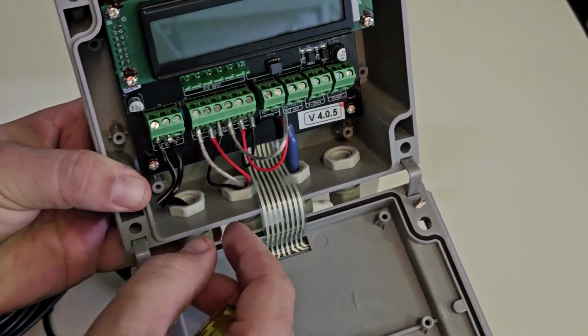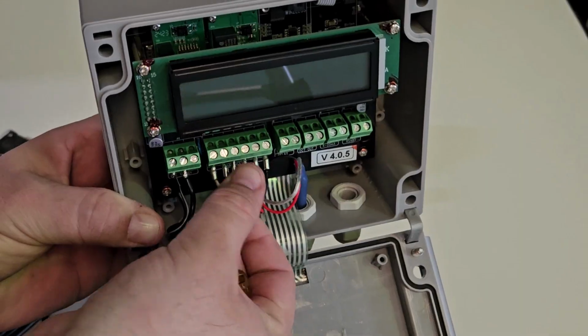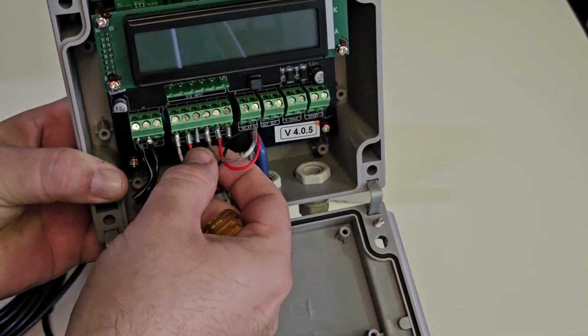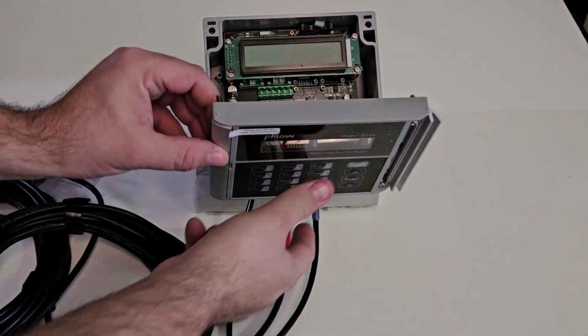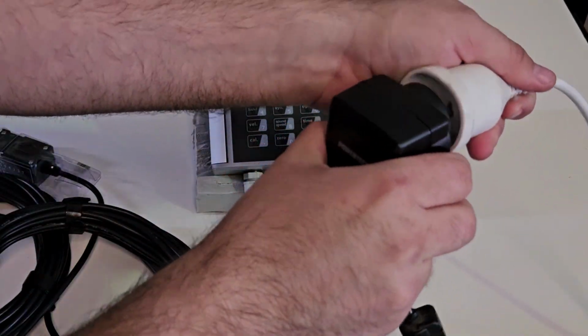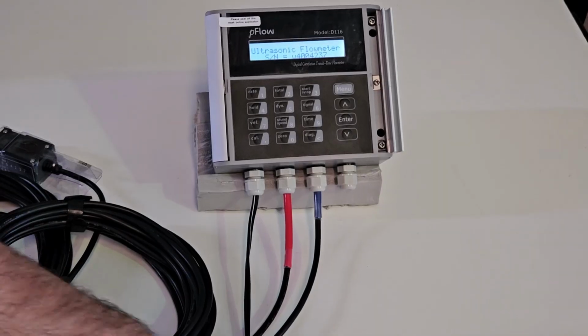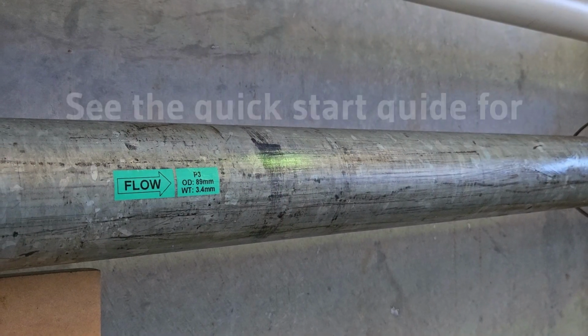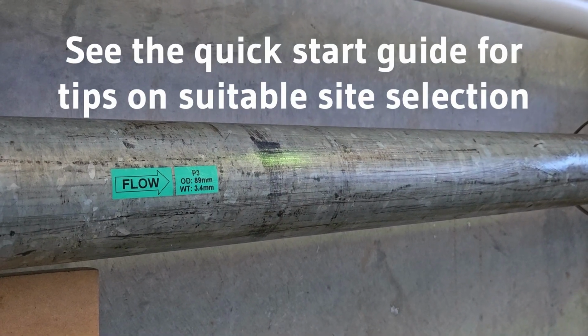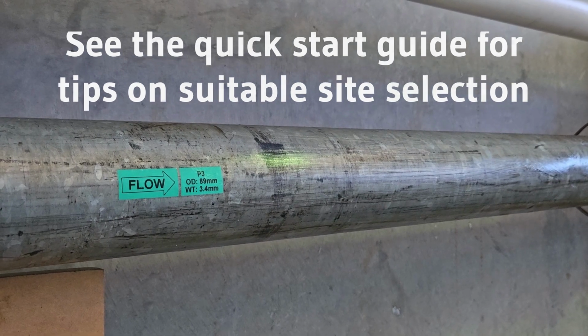Now tighten all of the screws for these wires, and ensure none of them are touching and the wires are tightly held. Now you can close the case, and plug in your power source. The meter will turn on as soon as power is connected. We will be setting up the flow meter for this pipe. We can begin configuring parameters on the meter accordingly.